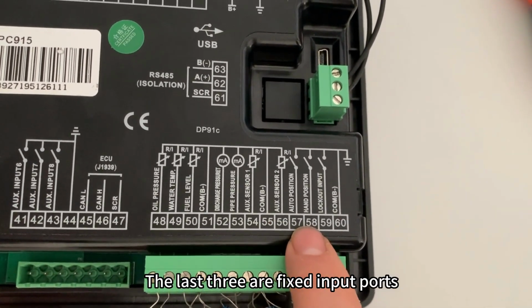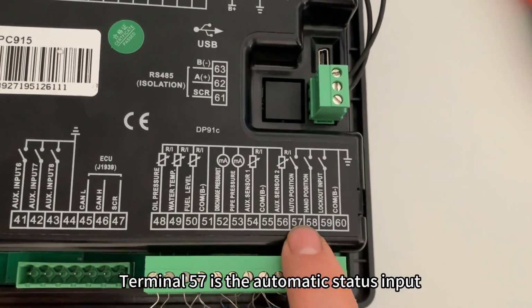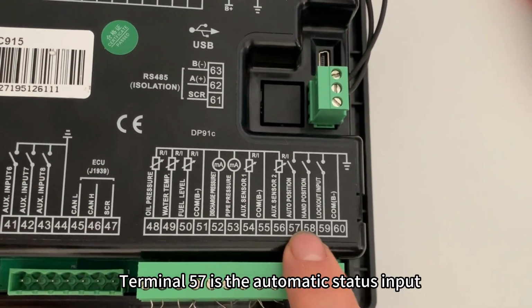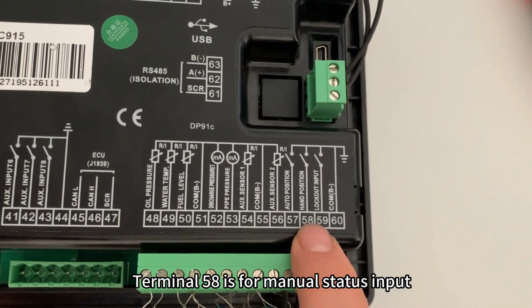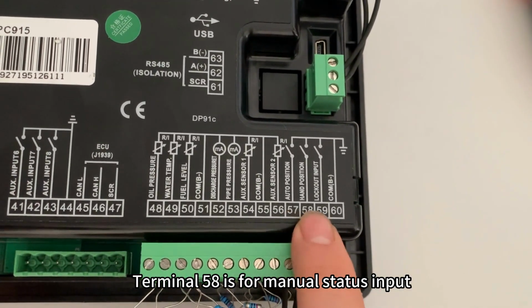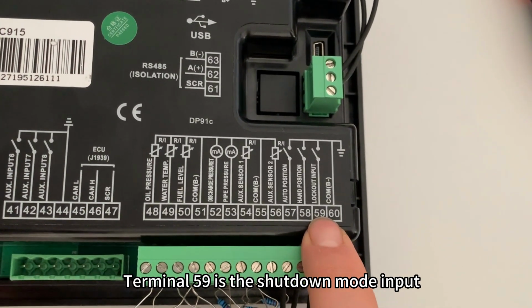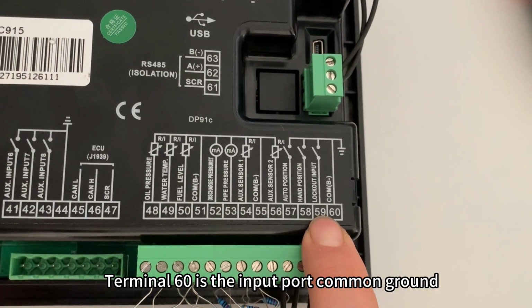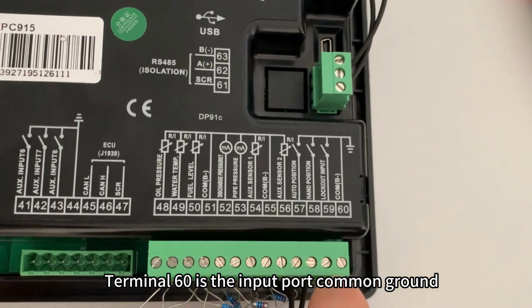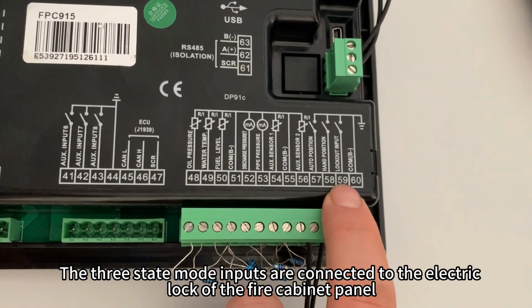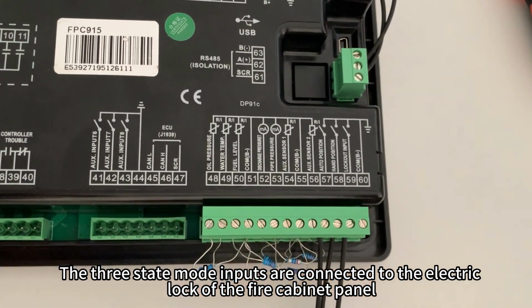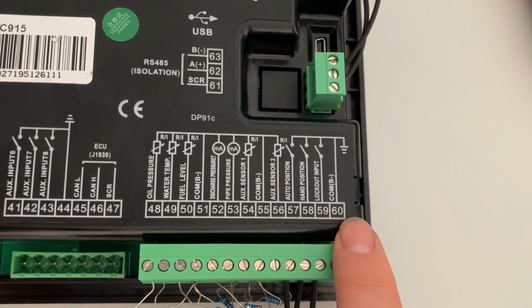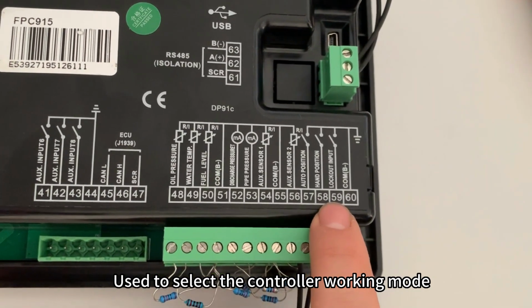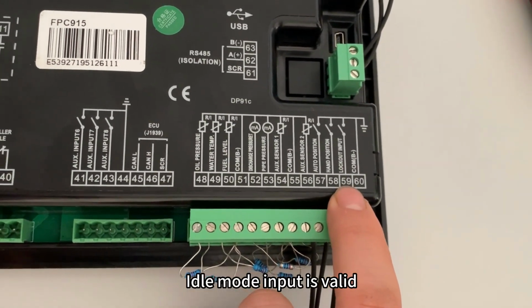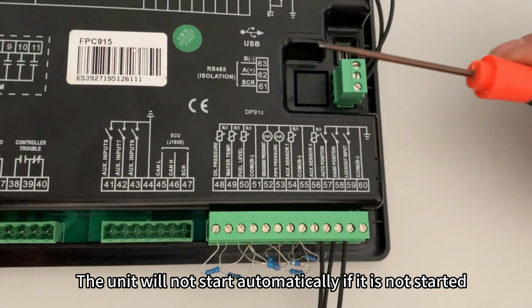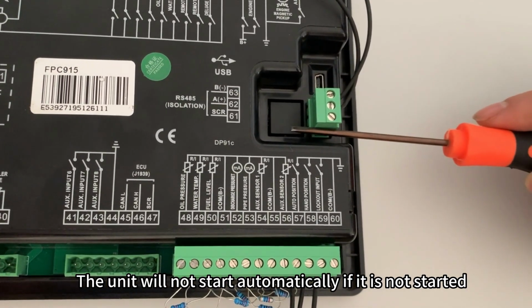The last 3 are fixed input ports. Terminal 57 is the automatic status input. Terminal 58 is the manual status input. Terminal 59 is the shutdown mode input. Terminal 60 is the input port common ground. The 3 mode inputs are connected to the electric lock of the fire cabinet panel, used to select the controller working mode. Shutdown mode input is valid. The unit will not start automatically if it is not started.